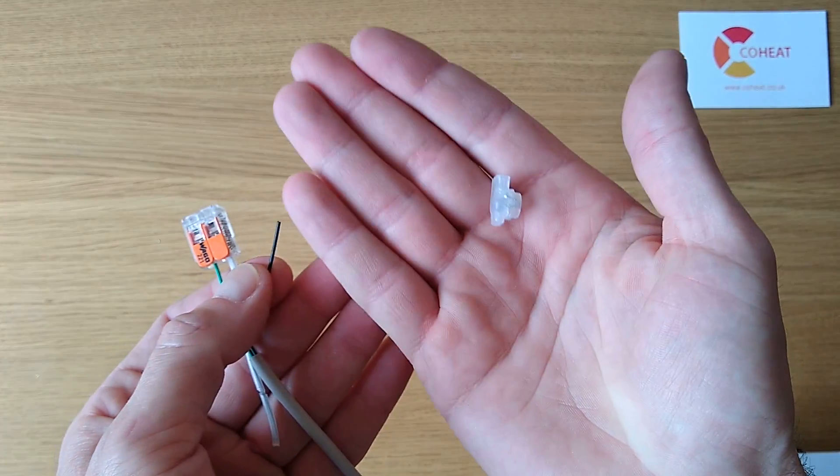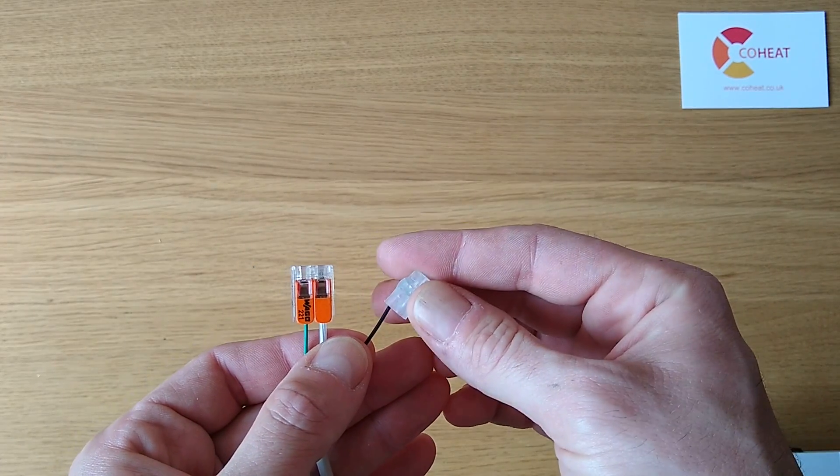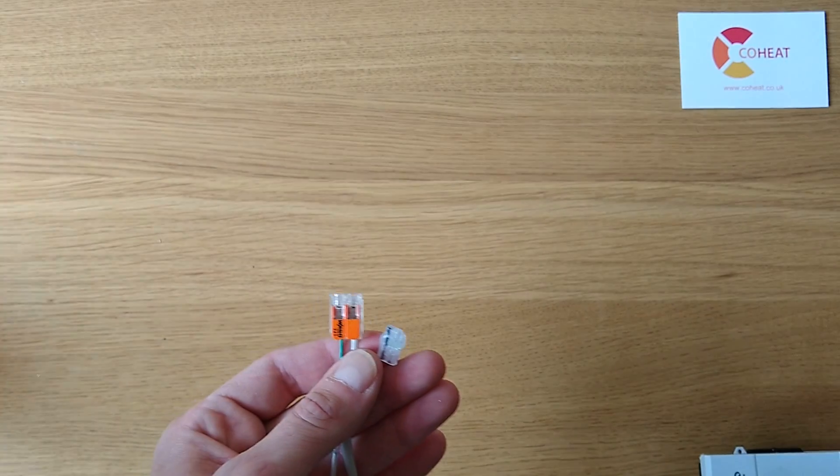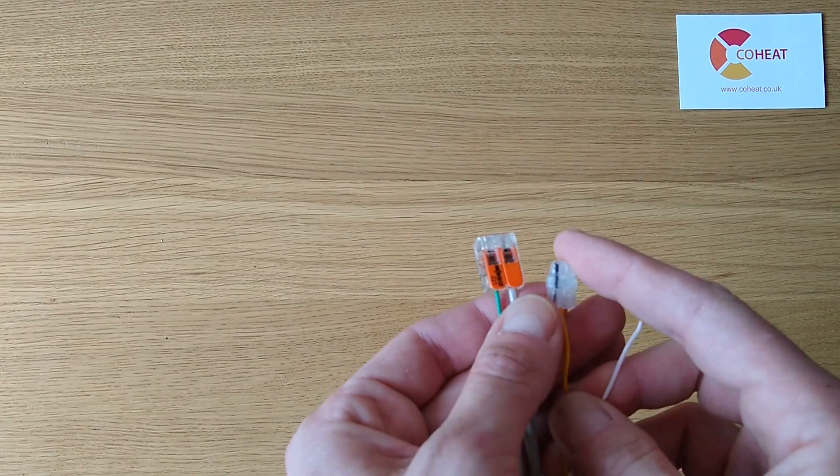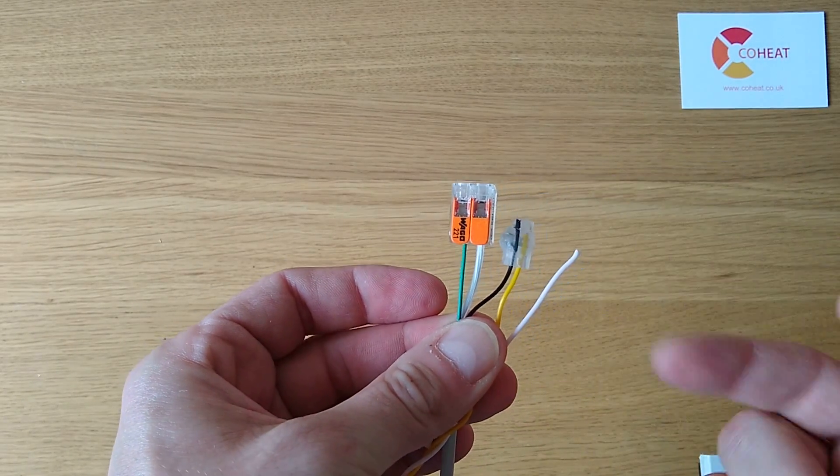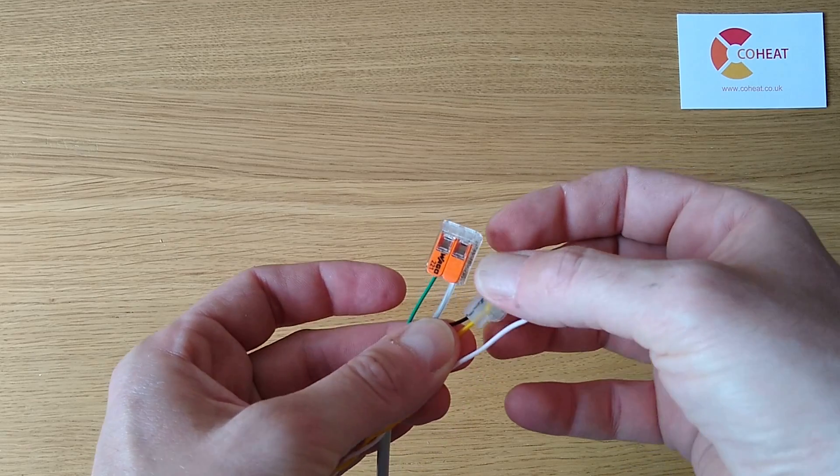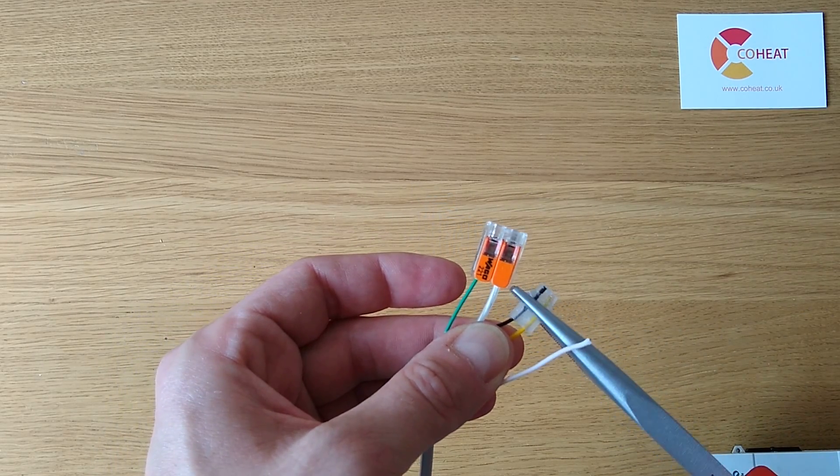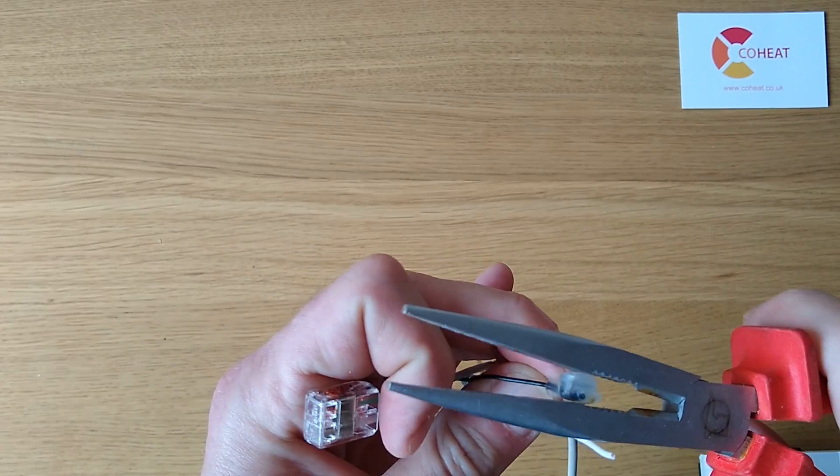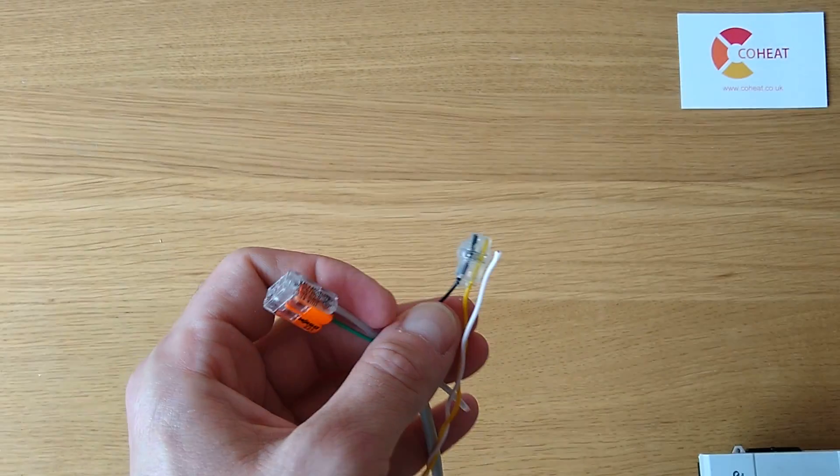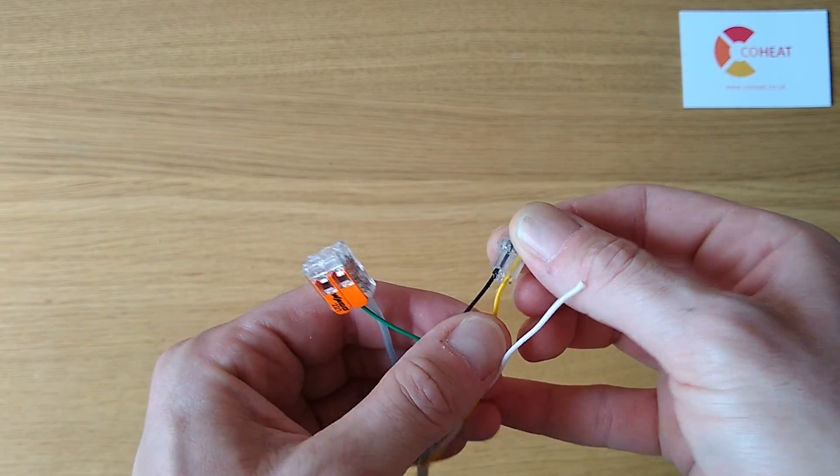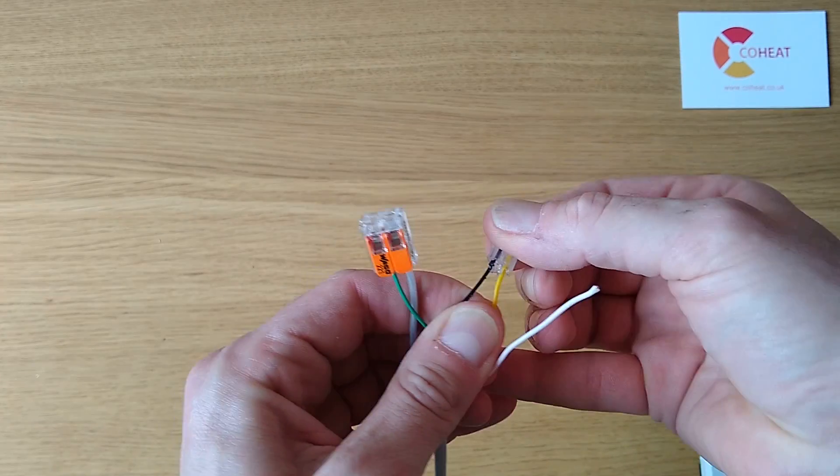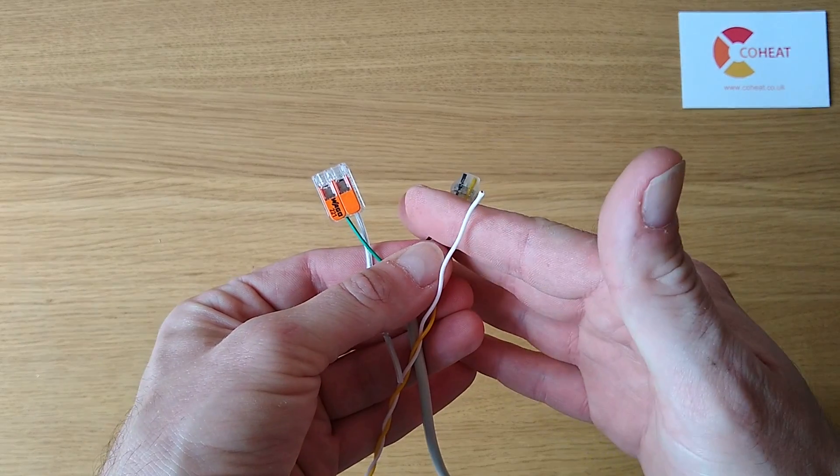The other option are these BT style jelly crimps. Pop one cable through here, pop your second cable in there, ensuring that they're all the way to the end of the connector. Then crimp with a pair of pliers, ensuring that you've crimped it all the way down. That is now waterproof, it's sealed with gel, it's cut the insulation and joined the cables, and it can't be stolen on site. If you do have to remove that, you have to cut the cable.